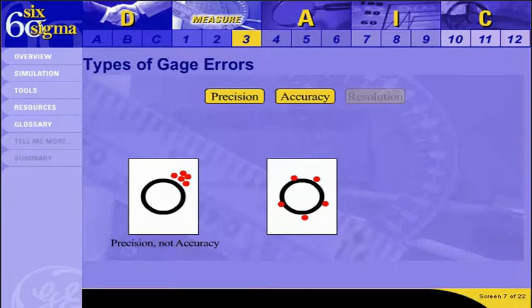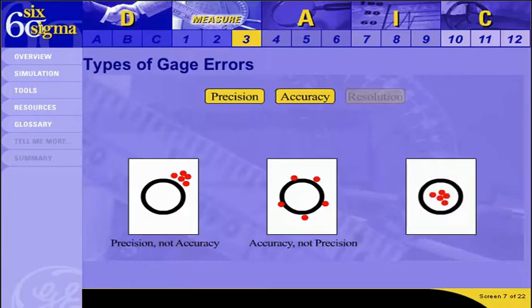Dots arranged around the center of the circle represent an accurate system but not a precise one — results are close to the target but quite distant from one another. A precise and accurate instrument produces dots that are close together and inside the circle, giving consistent results within the appropriate range. Problems with accuracy can be addressed by calibration of the instrument, while problems with precision can be addressed using a method called Gauge R&R, which we'll talk about shortly.